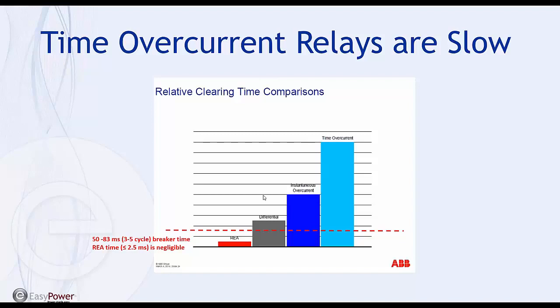And just to get into another slide, we have a very fast instantaneous element for our high stage, which is 20 milliseconds, but it's still, relatively speaking, quite a bit slower than the arc flash system. So even with the fastest instantaneous relays out there, you still run the risk of severe arc flash hazards.